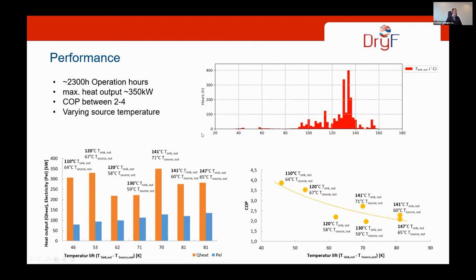And I've put here a couple of different operation points. On the left-hand side you can see the heat output and the electricity demand, and on the right-hand side the COP values, which of course depends a lot on the temperature lift. We have here from around 45 to 80 Kelvin, and the COP is varying, as expected, from 4 going down to 2.2.